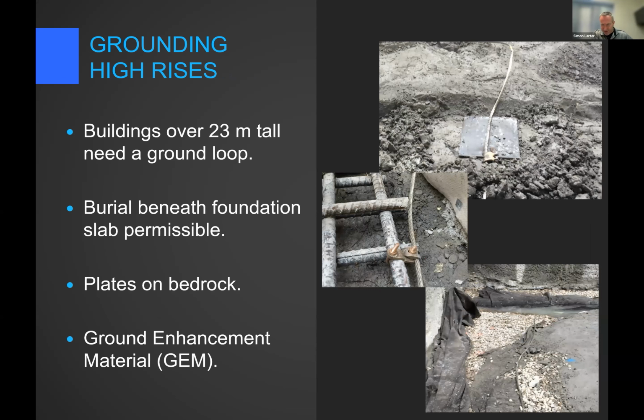I think that's the bedrock under Telesky. They dug down far enough under Telesky that they hit bedrock and then they had to chisel. So you can't really drive a ground rod into that. So what we did was we put ground plates down, we embedded them in ground enhancement material. Then we run a ground loop conductor around the outside, bonded to the rebar, and then they just backfilled the concrete over that. I think we were underneath the mud slab. So that is 100% permissible for lightning protection use. That's our ground underneath Telesky.